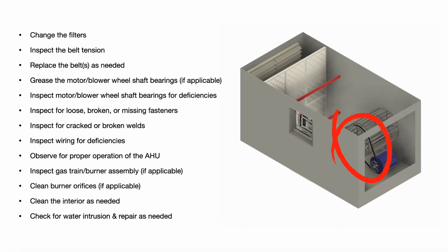Inspect the belt tension. You don't want the belts to be too floppy or loose. You also don't want them too tight because that could prematurely wear out your bearings and your motor. And replace the belts as needed, so if they're cracked or visibly worn. Grease the motor and blower wheel shaft bearings if applicable, like in this case. Or if you have a direct drive, then obviously that wouldn't apply. Inspect the motor blower wheel shaft bearings for deficiencies. Are the bearings loose? Is there a lot of shaft play? Are the bearings really tight and gritty and grinding or making a squealing noise?